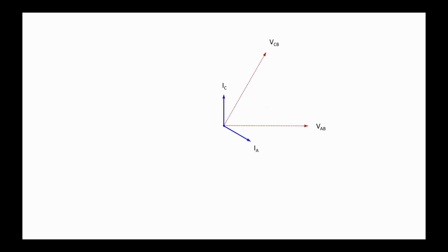Now all I'm doing in the next slide is rotating everything so that the A to B voltage shows as the horizontal axis, which resolves into the typical phasor diagram for a delta connected line. All right, take out the neutral conductor, take out the line to neutral voltages. This is what you're going to see on a delta connected line. This is only what you're going to see on a delta connected line if you're looking at VC to B.